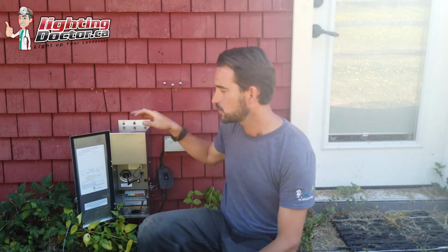But basically, in short, that's how you size your transformer. Add up the wattage of all your lights, and then just make sure you size that transformer about 20% higher. The less efficient, the cheaper the light, size it a little bit more.